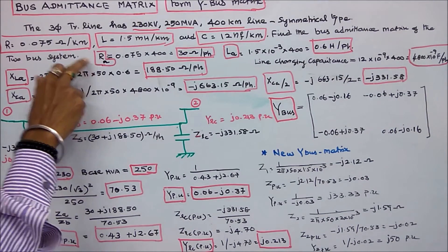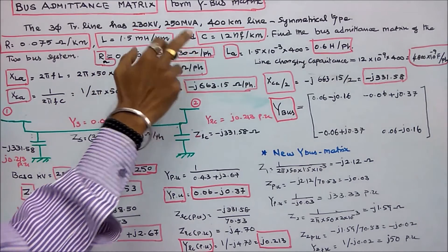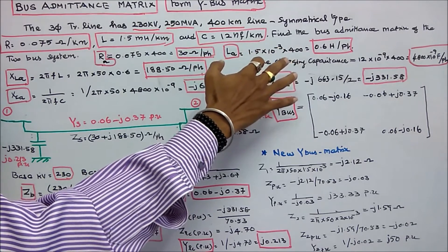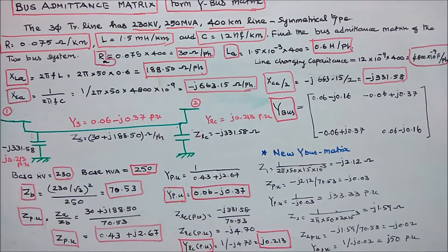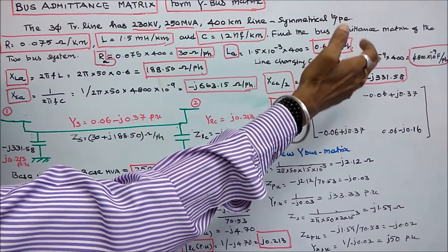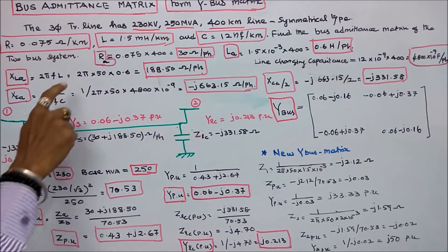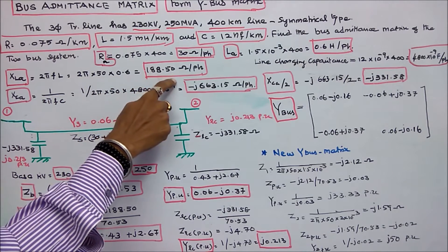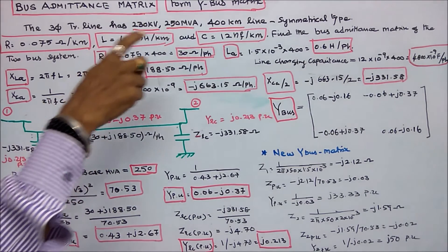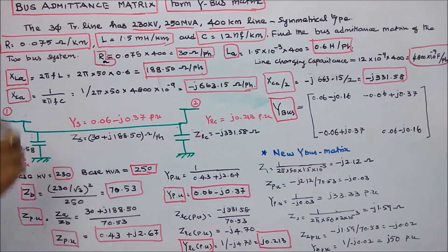Actual resistance is equal to 0.075 × 400 = 30 ohms per phase. Actual inductance is equal to 1.5 × 10⁻³ × 400 = 0.6 H per phase. Line charging capacitance is equal to 12 × 10⁻⁹ × 400 = 4800 × 10⁻⁹ farads per phase. Inductive reactance = 2π × 50 × 0.6 = 188.50 ohms per phase. Therefore series impedance Z = 30 + j188.50 ohms per phase.